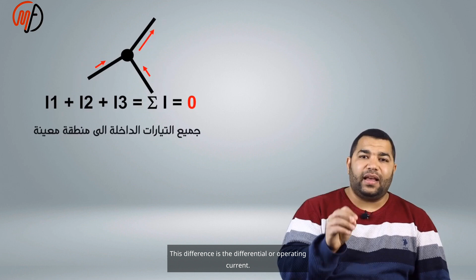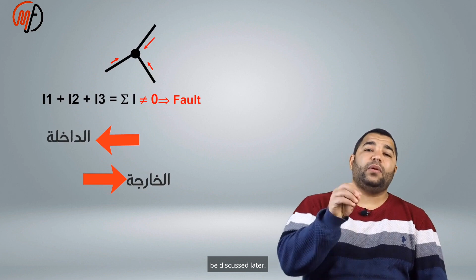Differential protection works by comparing incoming and outgoing currents in a protected area, based on Kirchhoff's first law. Incoming currents must equal outgoing currents. Any difference indicates a fault. This difference is the differential or operating current. The current balanced differential relay uses this principle. Voltage balanced differential relays, which measure voltage instead of current, are rarely used today and will be discussed later.